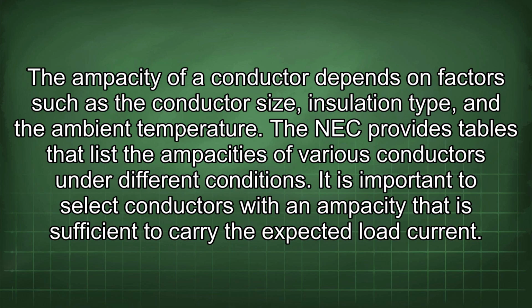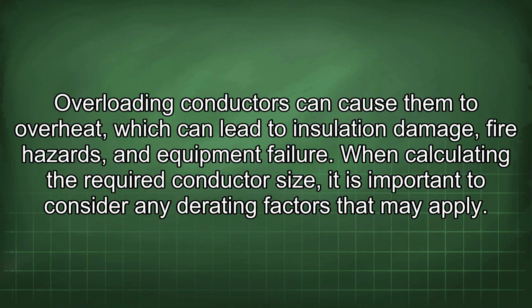It is important to select conductors with an ampacity that is sufficient to carry the expected load current. Overloading conductors can cause them to overheat, which can lead to insulation damage, fire hazards, and equipment failure. When calculating the required conductor size, it is important to consider any derating factors that may apply.